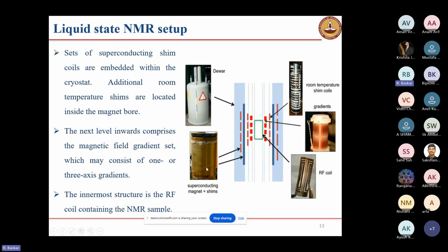This is the superconducting coil, and the magnet shims are here, and this is the probe and gradient. This is the radio frequency coil, and on top of the radio frequency coil we can see the gradient coils. The radio frequency coils are close to your sample. These are the room temperature shims. These are the things present in the magnet bore. One is the cryoshim, which is present in the liquid helium, in the cryogen itself, and the other is the room temperature shims, which are present inside the bore.